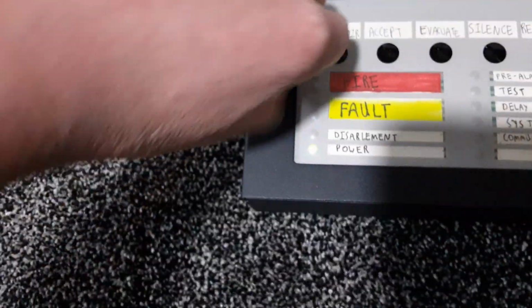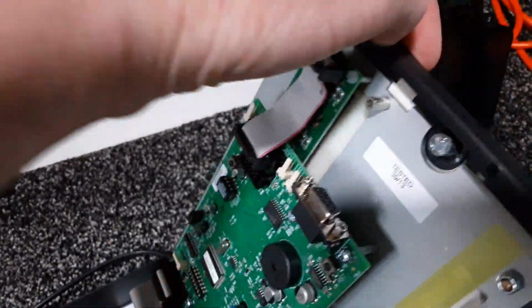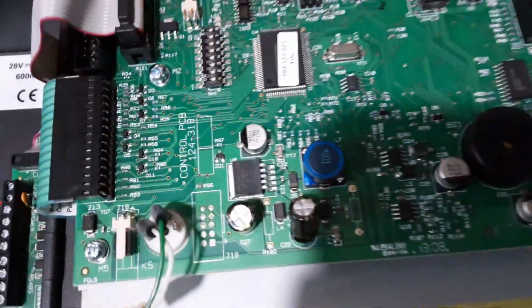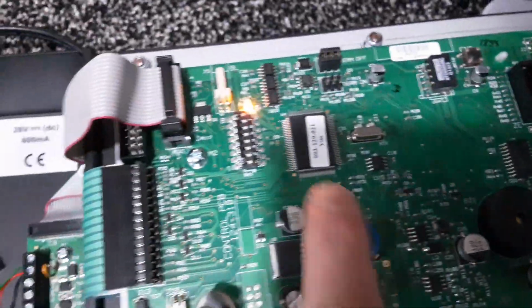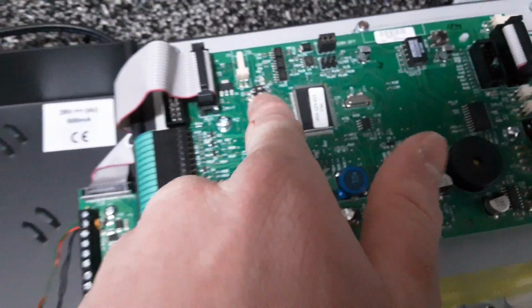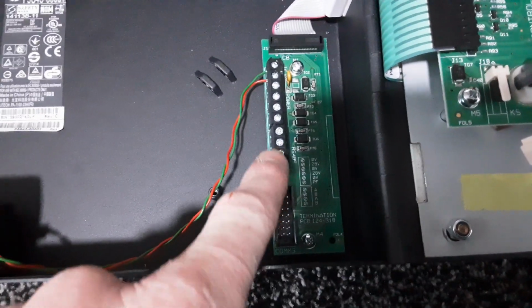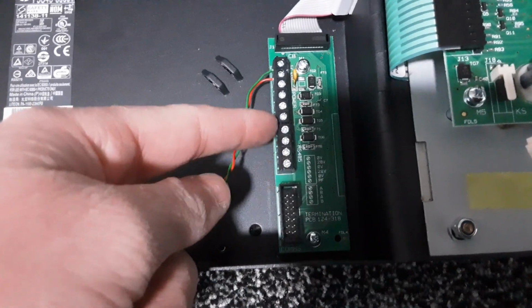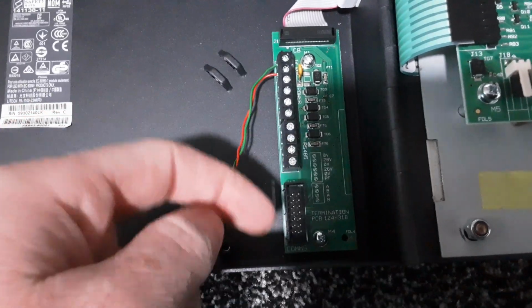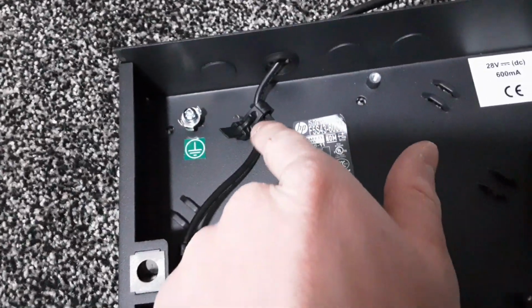So you've got to turn this. It's quite an unusual lock. Let's see. So there's the address switch. It's set to 0. I think that's a polling LED for when it's on the system it polls, because I think this full connector block here is the loop in and loop out. That's part of the addressable loop. That's the cable tie I was on about.